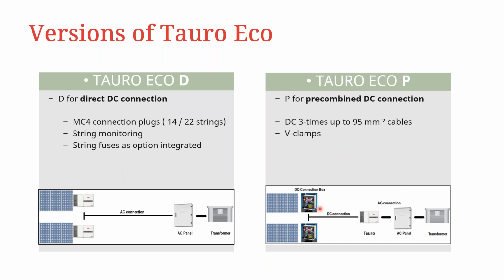With the pre-combined version, it means that you would then need a DC combiner box, and within the inverter, you have V-clamps that are provided for connection of DC power. For the 100 kilowatt version, we have 3 separation areas for DC power connection, and the maximum power cable connection in terms of size is up to 95 square millimeters.